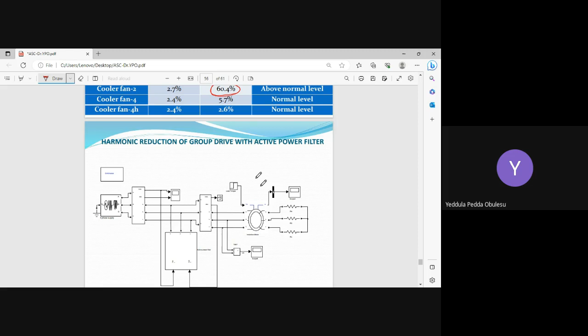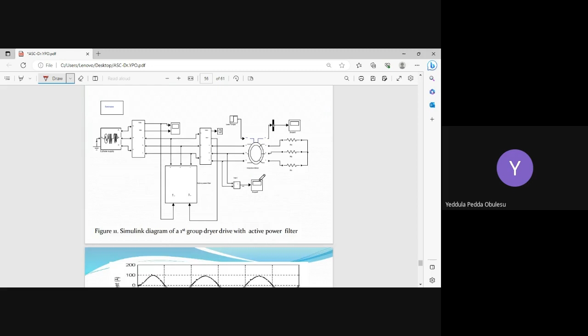Then we did the simulation study. In MATLAB we implemented this active power filter for the same cooler fan data. In the simulation we found that the harmonic distortion is reduced. At cooler fan 2, without the active power filter it is 60.4, and with the active power filter it is only 3.38. This was done only in simulation because at that time we did not have enough facilities to go for hardware implementation, and we could not afford the cost because of the high power rating.